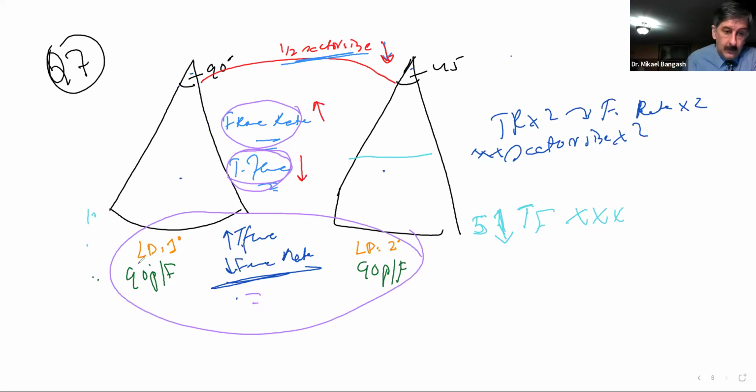So the only option that made sense here is that the line density was doubled, where we end up with the same number of pulses per frame, although the sector size was reduced.